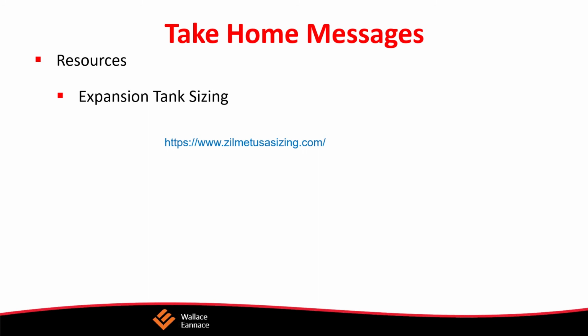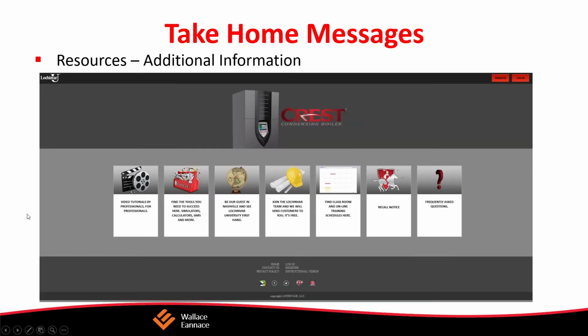Here you can see some of the basic screens. It shows you the water temperatures, the delta T, the outlet water temperature, whether or not the flame is running, flue temperatures, premix temperatures, set point, what the status is, what's happening, where it's modulating at. So the Connexus is really powerful. It works hand in hand with the smart system and gives you full control of the boiler and the system as a whole. So let's take home some messages.